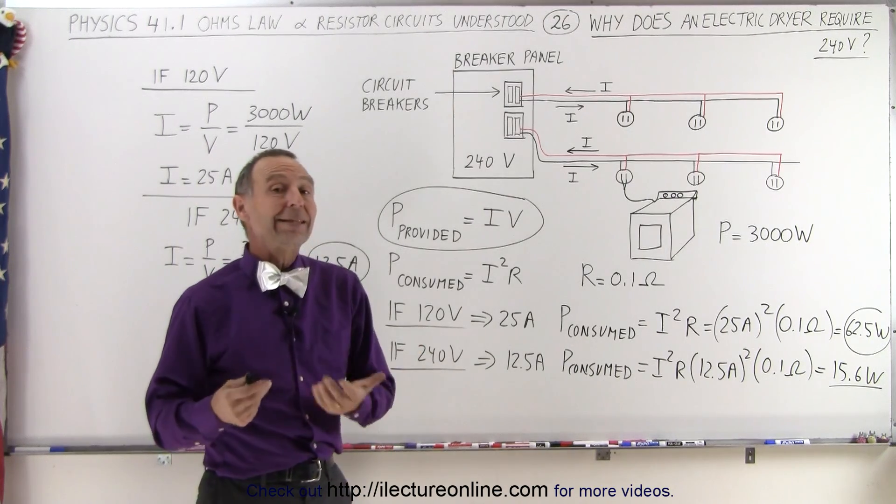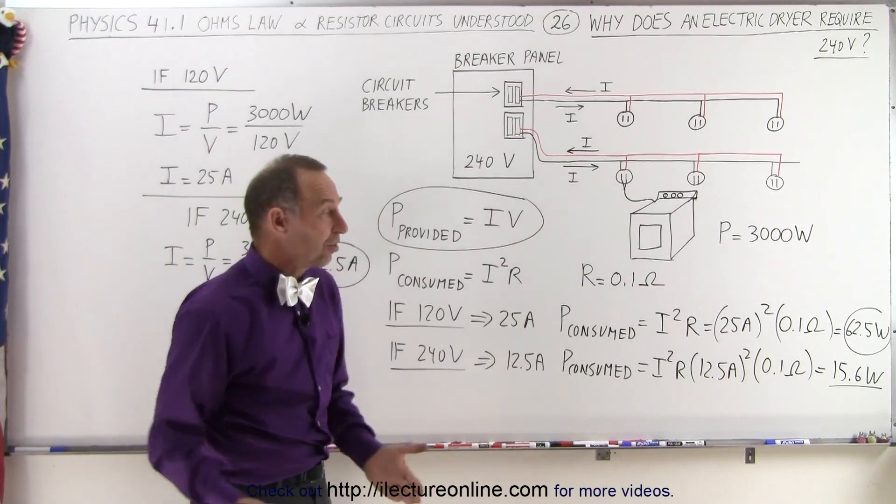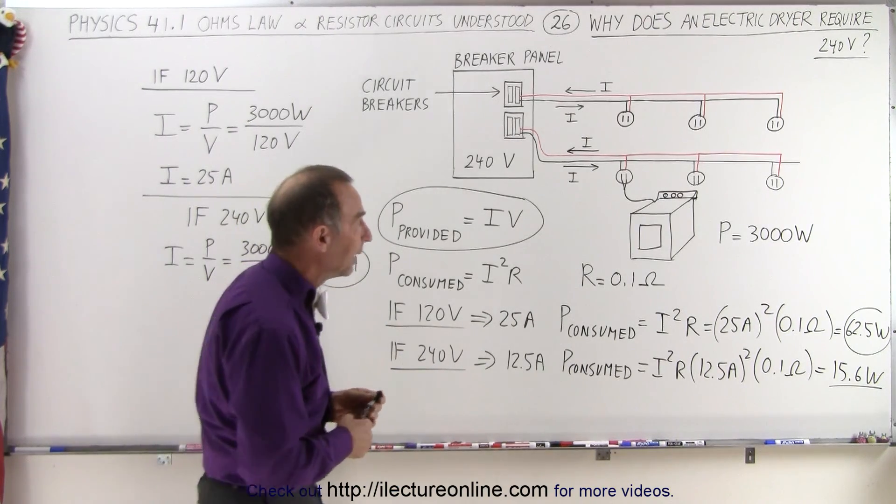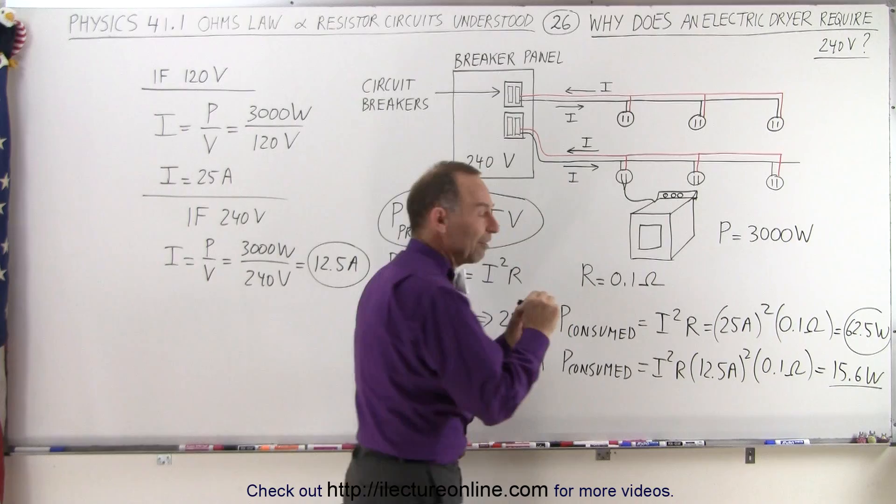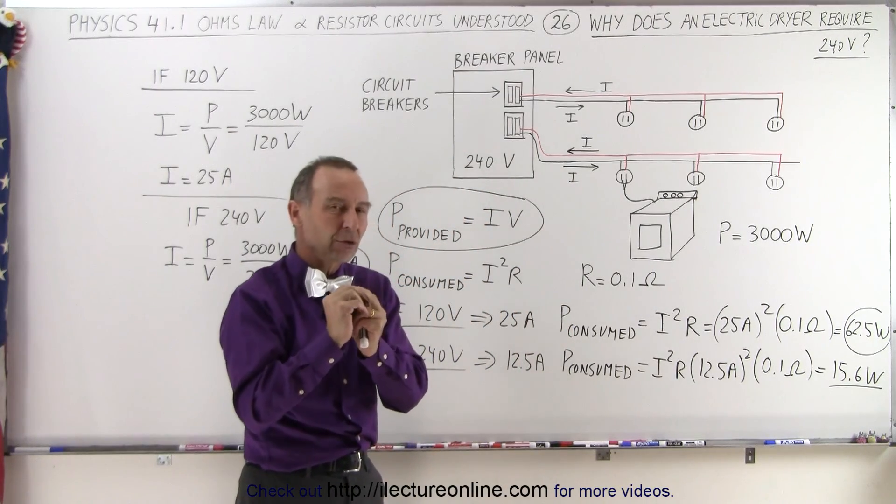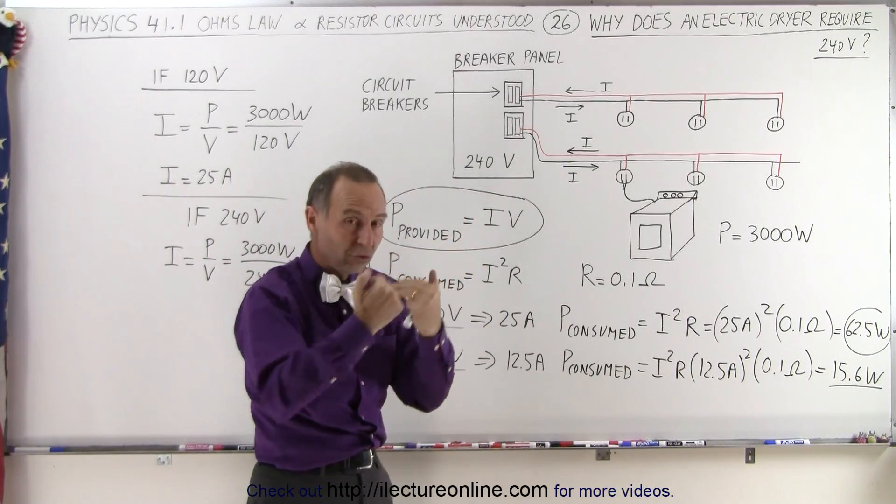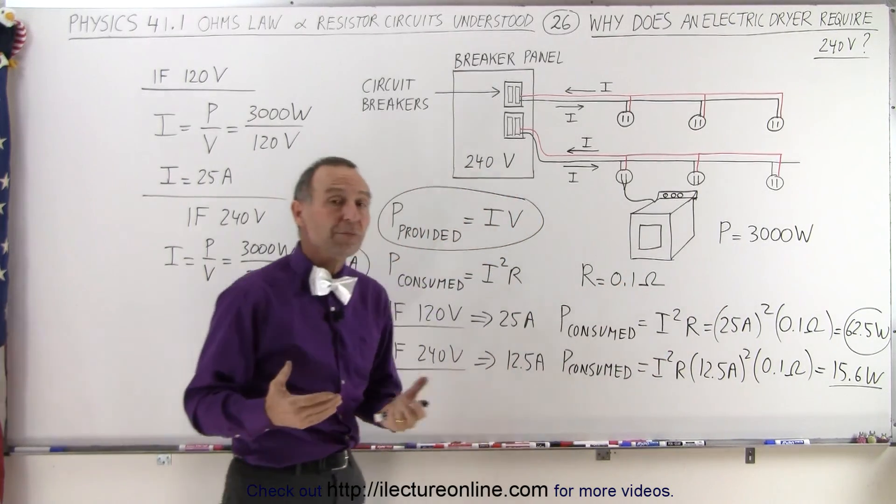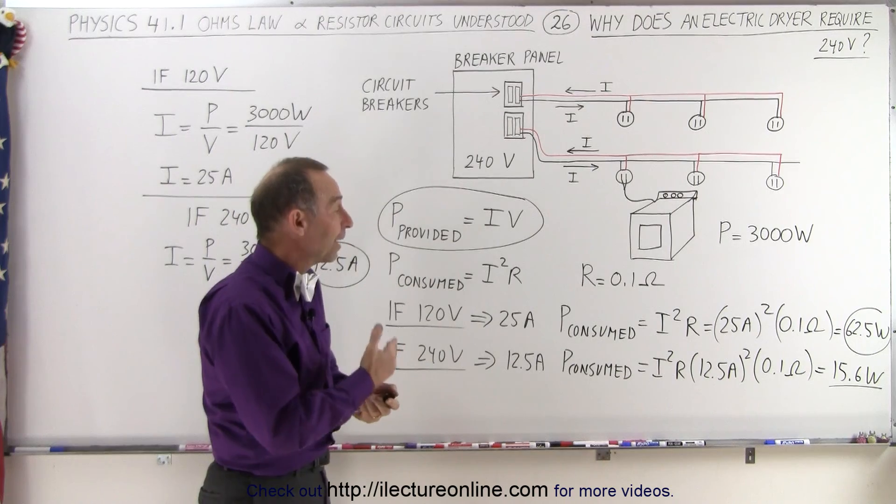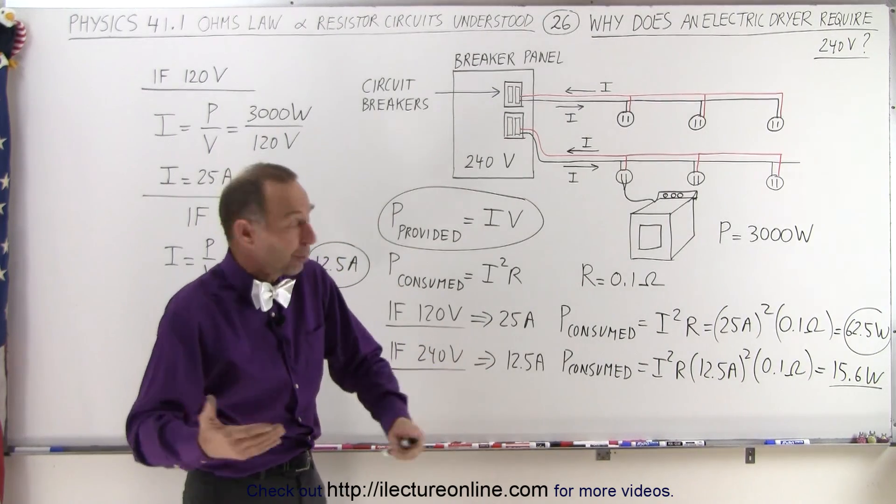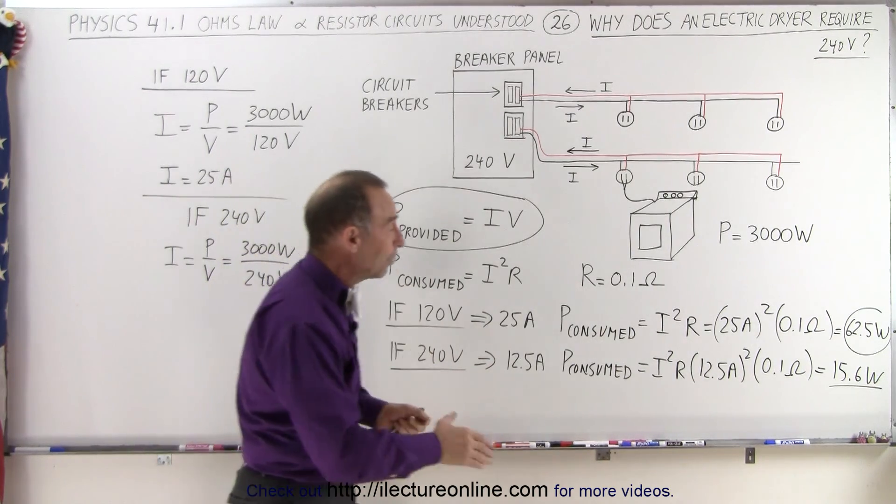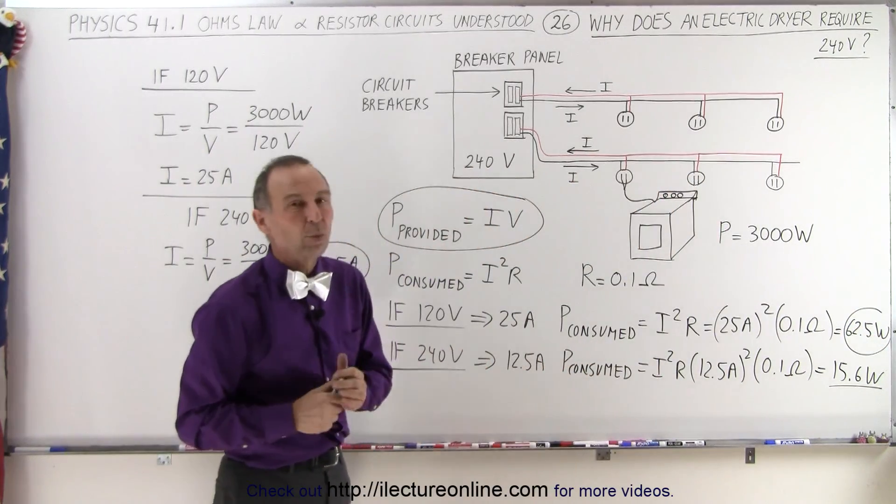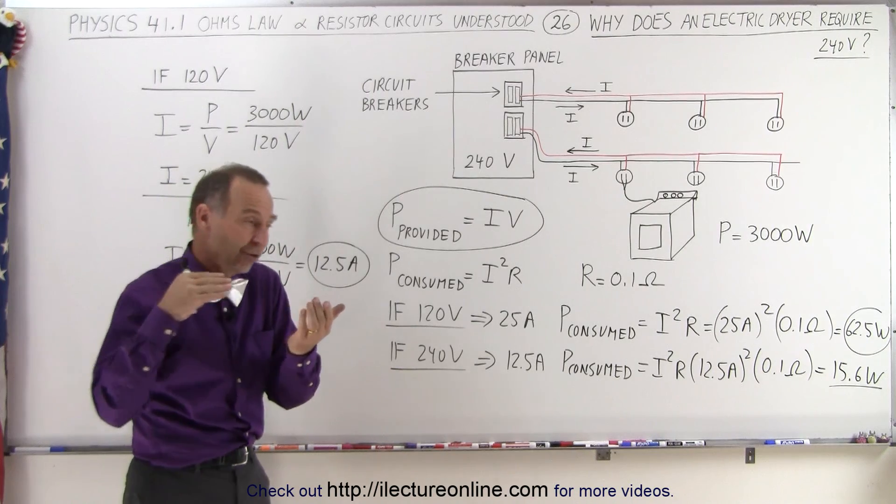Another thing that they do when you have big appliances like electric stoves or electric dryers hooked up to a circuit: they will actually use wires that have a much bigger gauge, a much bigger cross-sectional area, reducing the resistance. So instead of maybe having a wire that for a certain length is 0.1 ohms, it may only be half of that - 0.05, or maybe even 0.02 or something like that - again reducing the power consumption of the wires so they don't get nearly as warm.